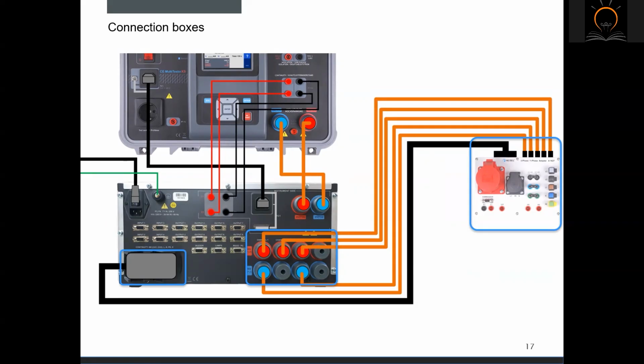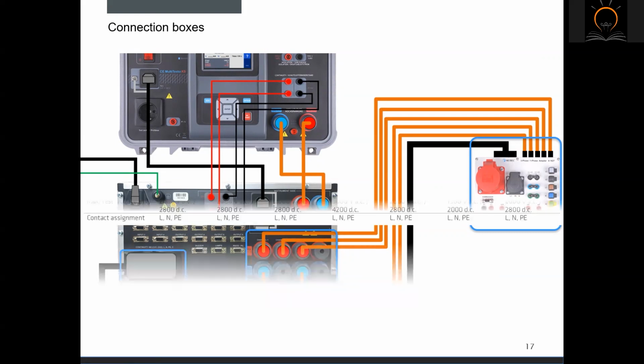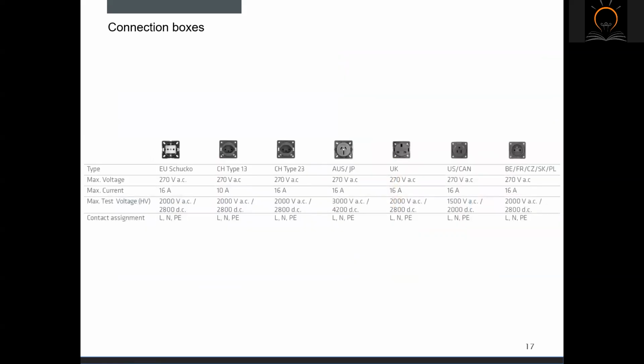Each type of connection box has unique code identifier, which is important for the possible testing options, including some predefined maximum characteristics, such as maximum withstanding test voltage or maximum current for each continuity measurement that could be applied to tested appliance. Connection boxes are available with different socket configurations, depending on the requirement of a particular country. Contact Metrel for ordering specific version of the test socket.